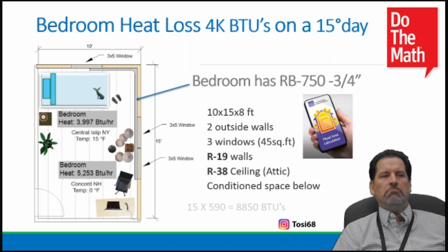We need to know 97 point something percentage of the time, the coldest day of the winter won't be anything more than 15. It can get colder, but that's a high percentile that we should kind of shoot for. I think they've been taking these numbers since like the mid 60s or something. 4,000 BTUs is what this room requires on the coldest night of winter.